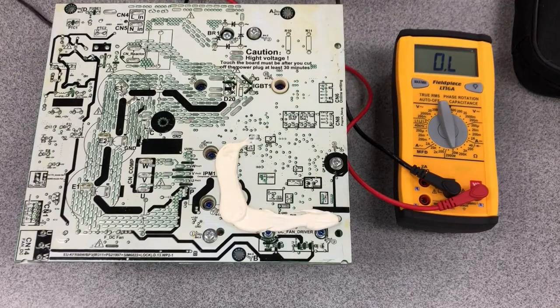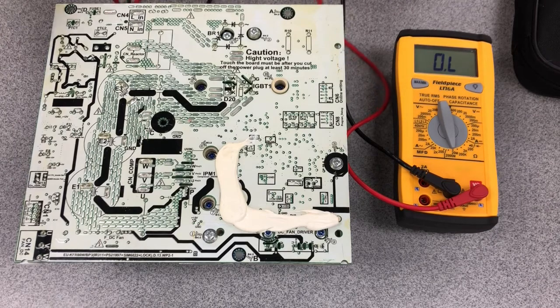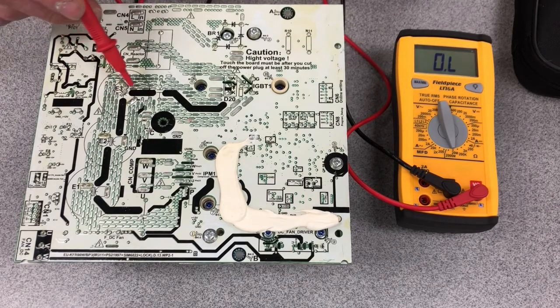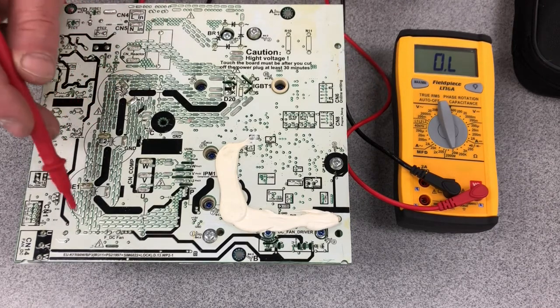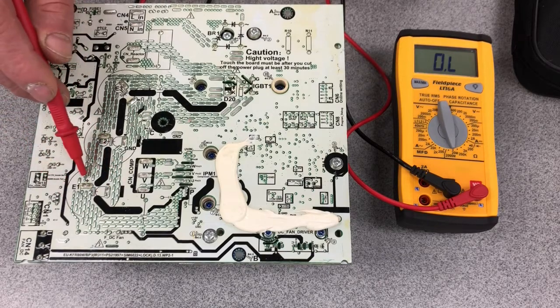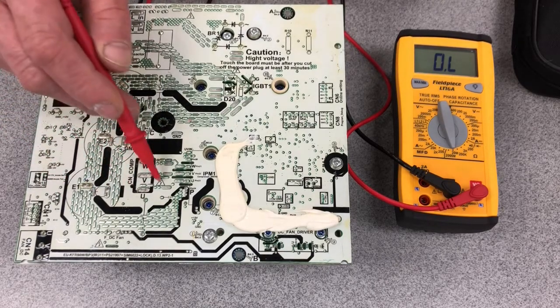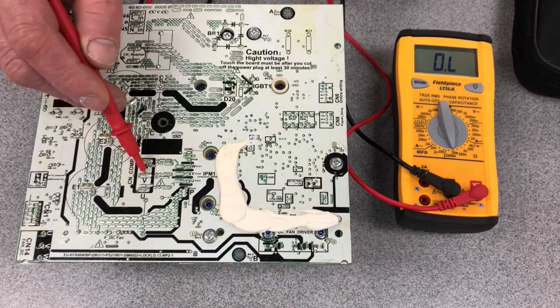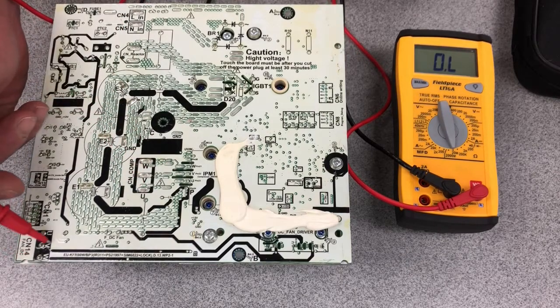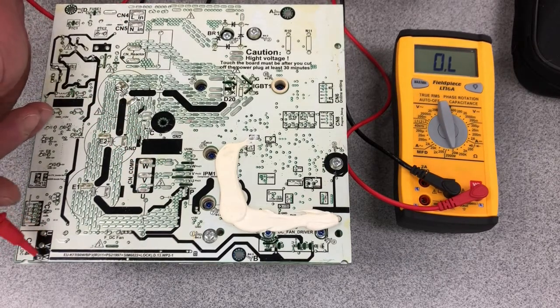I've taken the board out of the unit so you can see it. First thing I'm going to do is find my negative and positive - just look for the capacitor circles. There's my positive, there's my negative. There's my compressor terminals, U, V, and W. Over in this corner are the terminals for my condenser fan, U, V, and W.